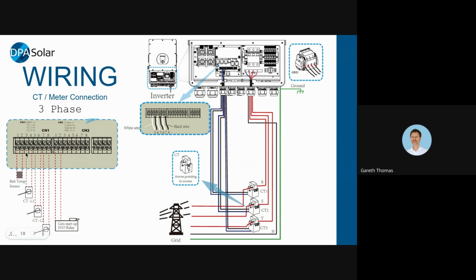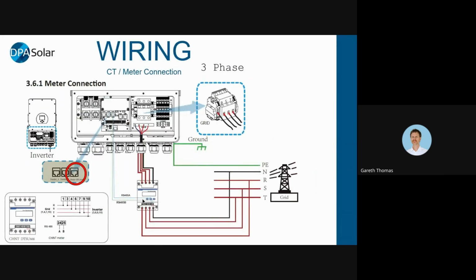Okay. So this is where the CTs attach in here. Just push them in. And then obviously they're going around each of your three-phase actives, and again, with the arrow pointing towards the inverter. If you don't want to use the CTs, again, you can use a three-phase meter, and that gets connected to the meter port.